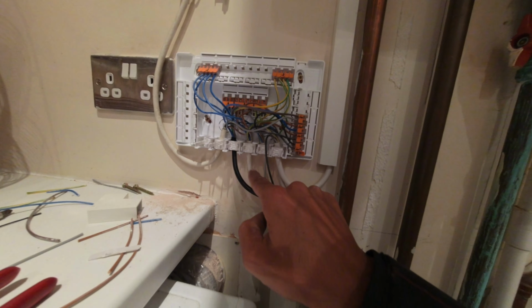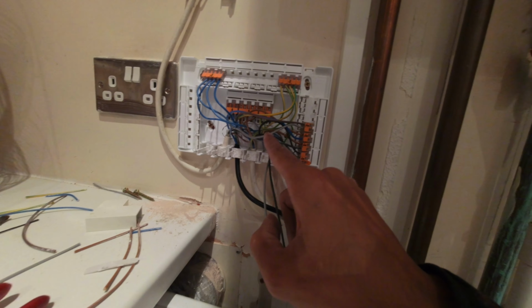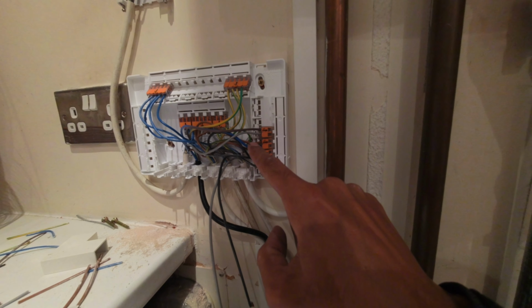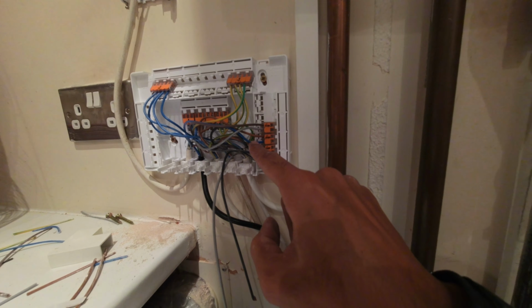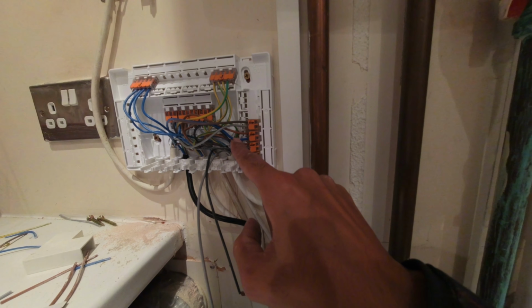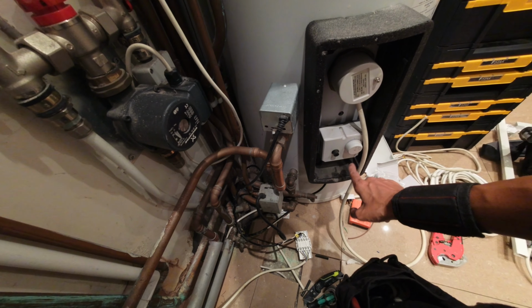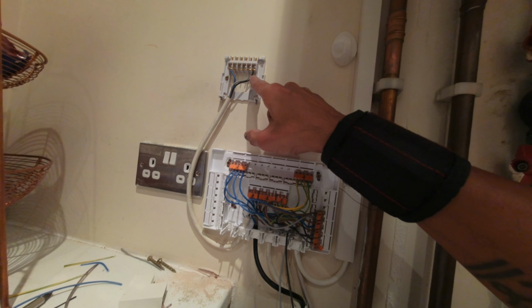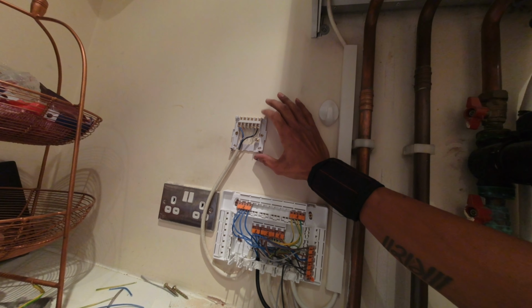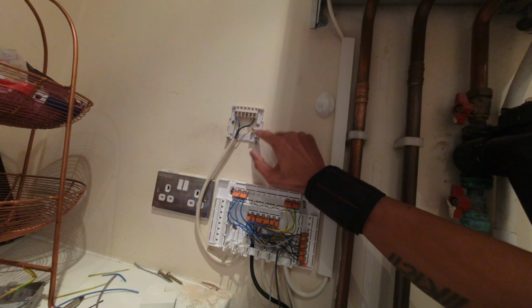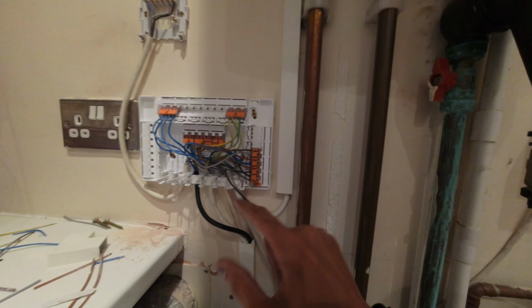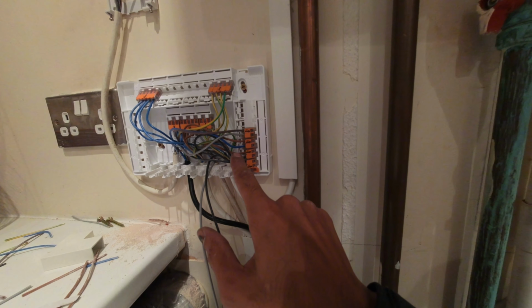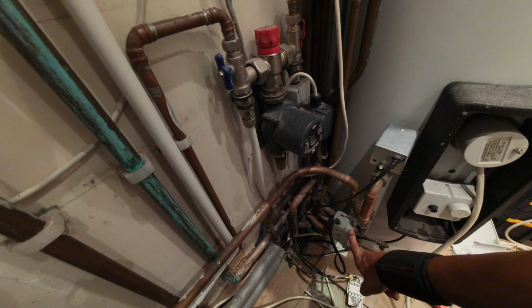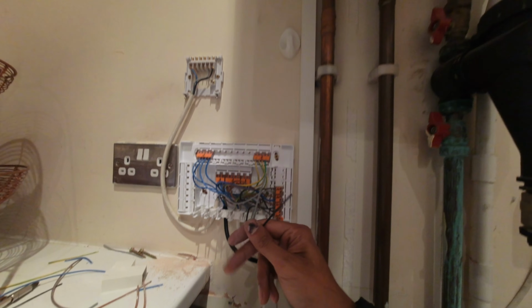inside the cylinder stat. And then this is our hot water cable, so that's going to be the second one. That's the brown coming from the hot water zone valve, and that's linked to the call from the cylinder stat, so that's the blue one. That's coming off of the demand terminal from the cylinder stat. And then the heating, because this basically is the receiver, so when the thermostat clicks on, that black cable from number 4 goes straight to the brown on the heating zone valve, so that will then activate that and get that to come on. All I've got to do now, I just need to open up the boiler.